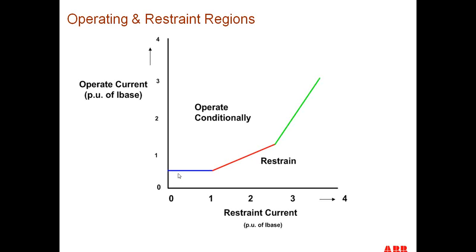On most relays, these points of the curve, the minimum operate point, the break point between the 0 slope and the 1 slope, and the break point between the 2nd slope and the 3rd slope, are all settable values, and the percent of the slopes is also settable. But for 95% of the applications that you would have for current differential relays, you can leave it at the default values of 40% and 80% for the 2 different slopes.